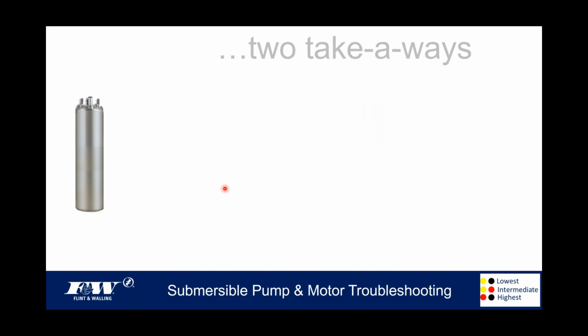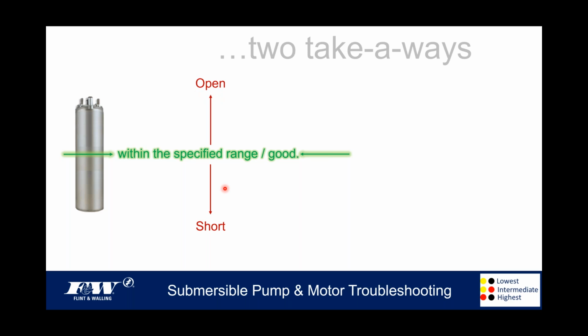So a couple takeaways, and I'm going to close this off. I see I'm at 3 o'clock. Anytime you put a test on a motor or drop cable and a motor, and you're coming in within specified range, that's always good. That's always a good thing. However, if you are coming in lower than that specified range, that's going to indicate a short. If you're coming in higher than that specified range, that's going to indicate an open winding. And as we just talked about, if you're coming in both ways, you're mixed up. You got mixed leads, right? Mixed leads. So hopefully that little chart right there will be a good takeaway for you.